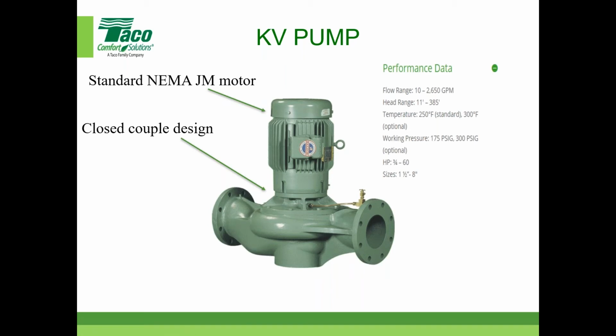And one thing I always like to mention, we have different model numbers. So I may have a KS 3007 with a 10 horse motor and a KV 3007 with a 10 horse motor at the same speed, 1760 or whatever. The performance of those two pumps is identical. Keep that in mind, the curves for these two pumps are identical. So that means the wet end, the internals, are identical. Hopefully that all makes sense.